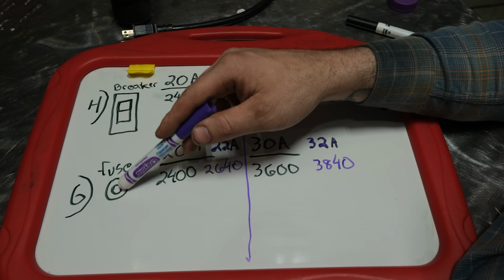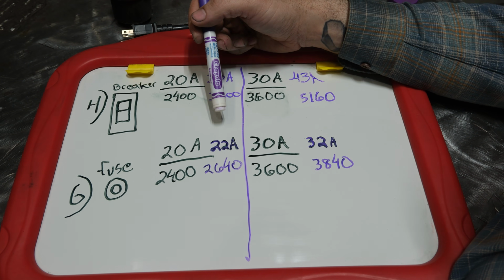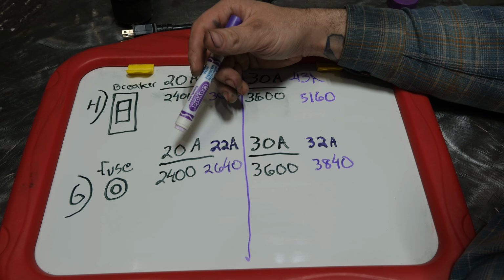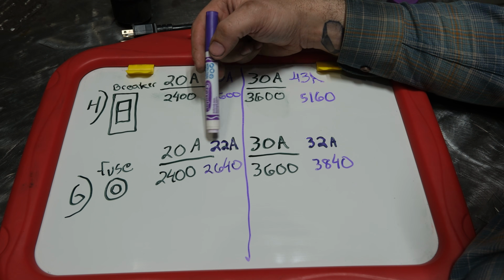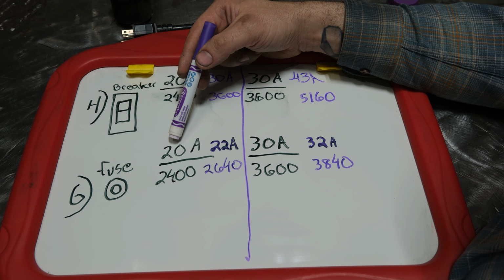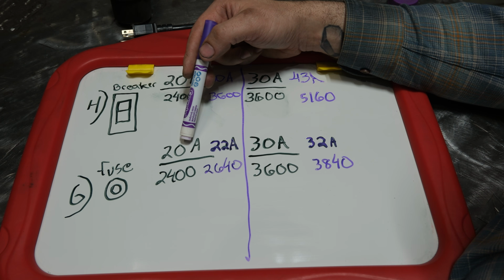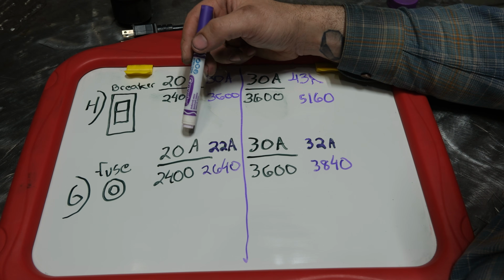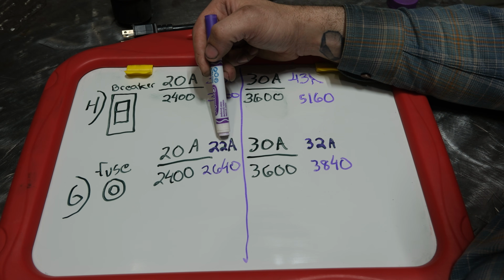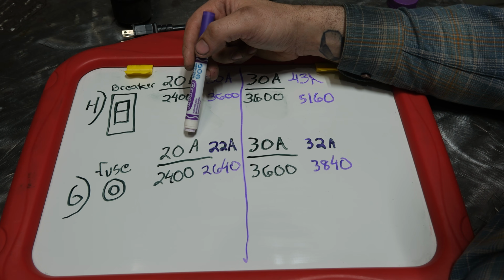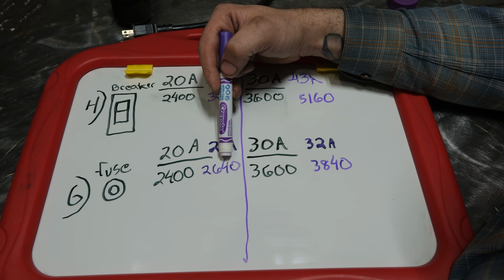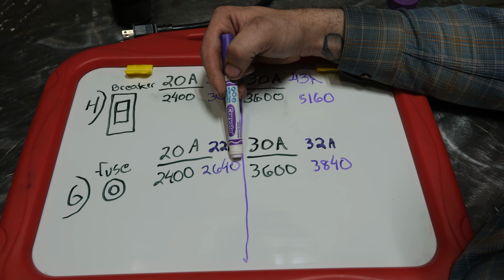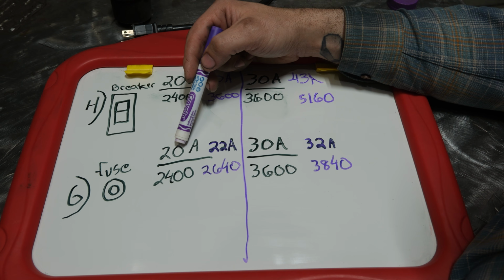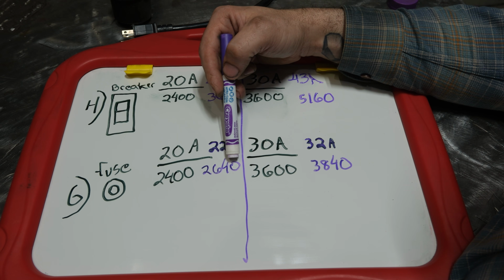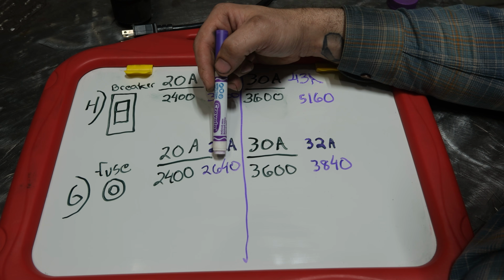So the fuses, which are typically the round fuses on your generator, some of them have breakers similar to a house, doesn't matter. All of those trip much closer to what their rating is on the face value. So a 20 amp rated round resettable fuse is pretty much going to trip at 22 amps. And my guess is it might even trip exactly at 20 amps. So you're only going to be able to pull 2,640 roughly out of a 20 amp circuit on your generator before that breaker just trips. Now you can see a problem with that.